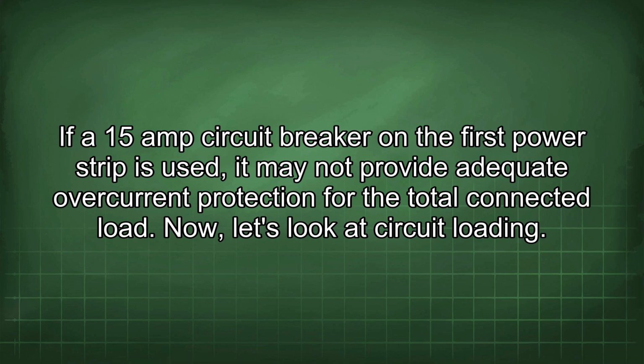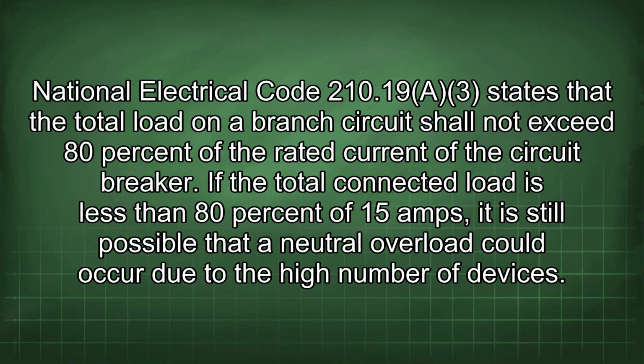Now let's look at circuit loading. National Electrical Code 210.19 states that the total load on a branch circuit shall not exceed 80% of the rated current of the circuit breaker. If the total connected load is less than 80% of 15 amps, it is still possible that a neutral overload could occur due to the high number of devices.